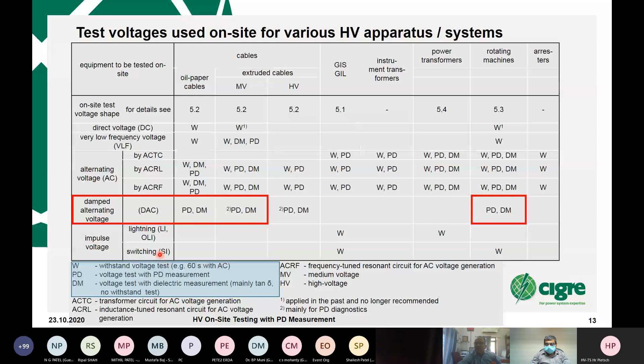it's allowed everything: PD, diagnostic and monitoring, and all AC, independent of how it's produced, 50 Hertz or 60 Hertz, or slightly between 20 and 300 Hertz for the resonant frequencies. And as I said, this is defined by IEC 60060-3. It allows other frequencies, so it's allowed for withstand test and PD, and this is for the power equipment in operation. The damped AC is a damped AC voltage. We will see later how it looks. Again, it's for monitoring and diagnostics, but not for a withstand voltage, because it's not a continuous sine wave, and so the equipment is not stressed as it should be. And then there are some others, lightning, oscillating and switching, which are not part of my presentation today.